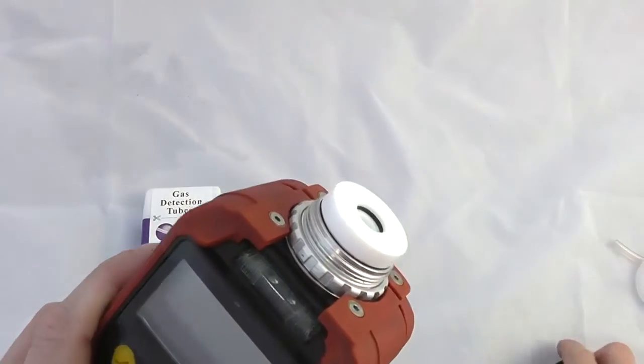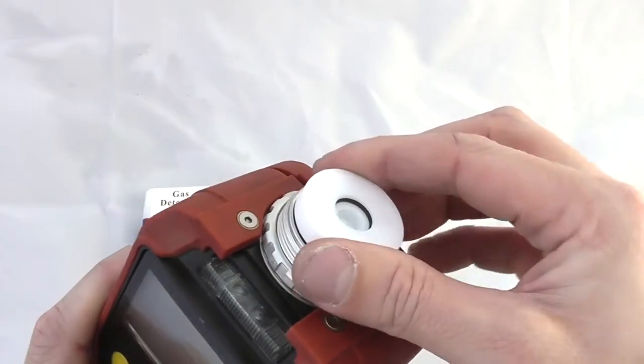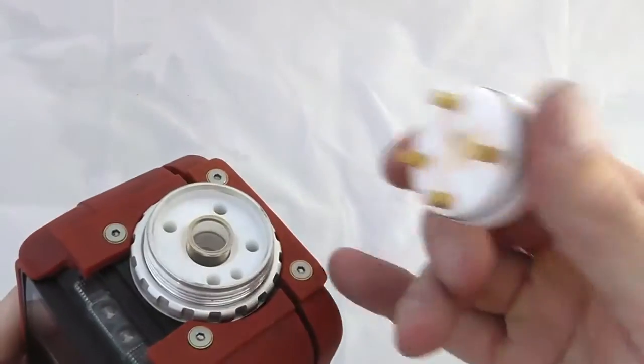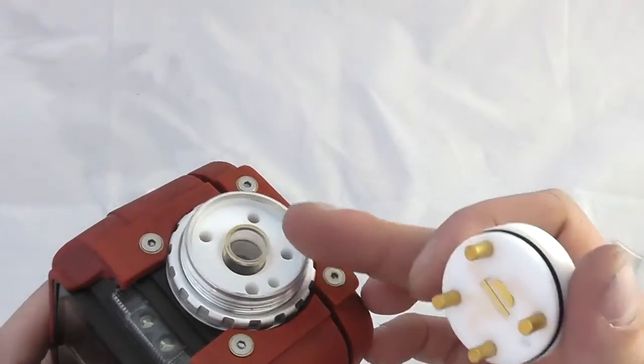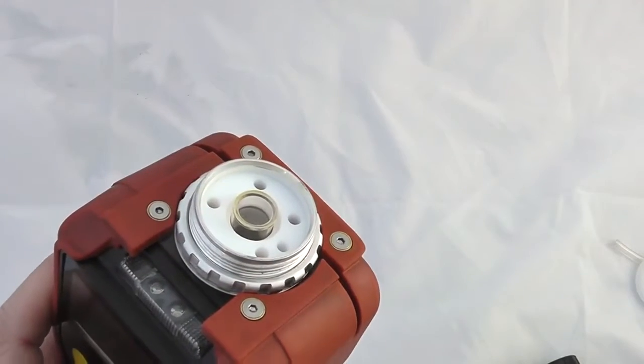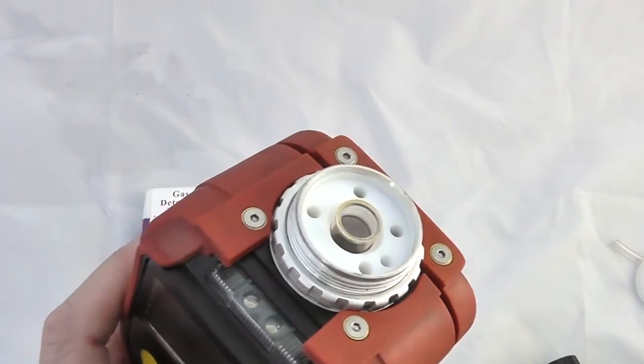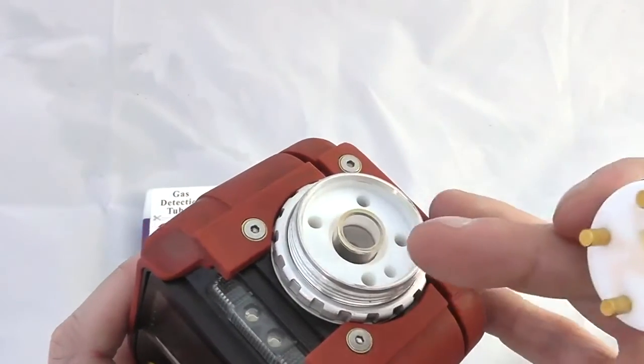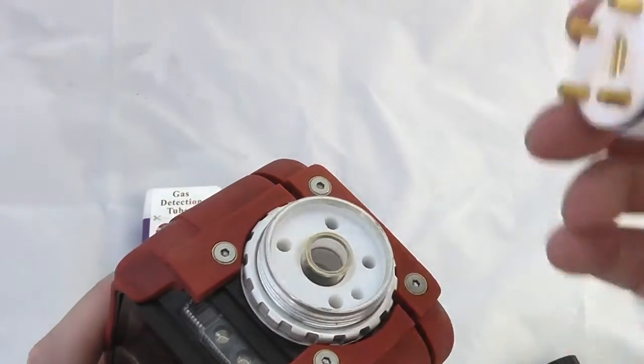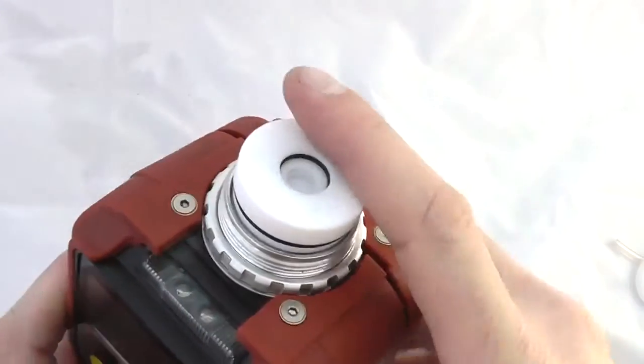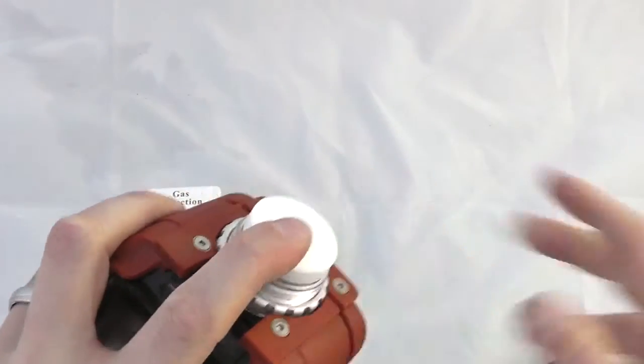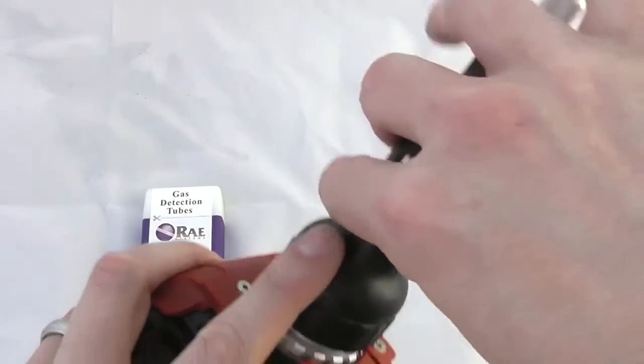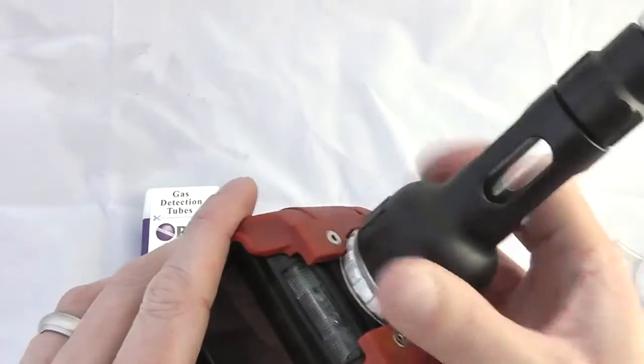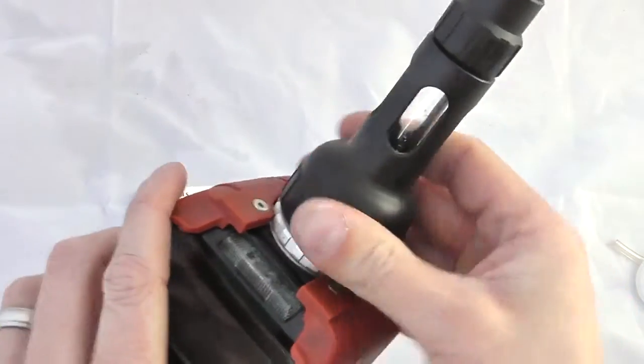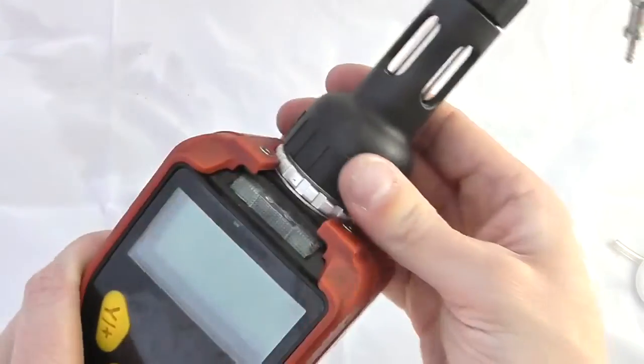Now a lamp clean is something I would recommend doing. You can remove the sensor block, it simply pulls out of the instrument, and then you can see the lamp is exposed. It is important not to touch the lamp with your fingers, it will become contaminated over time, but you can use the lamp cleaning solution to just clean over the top of the lamp. The other thing to bear in mind is the lamp cleaning solution actually contains VOCs, so it is important to leave the lamp exposed and to dry off after you have done a lamp clean on it. And then we just reattach the tube assembly and we are ready to go again.